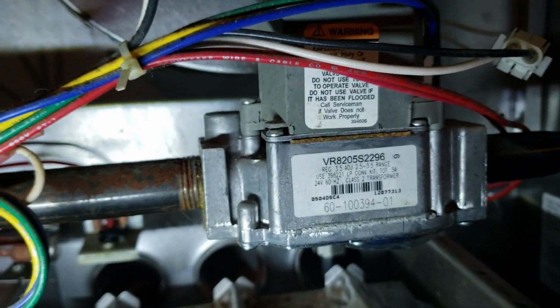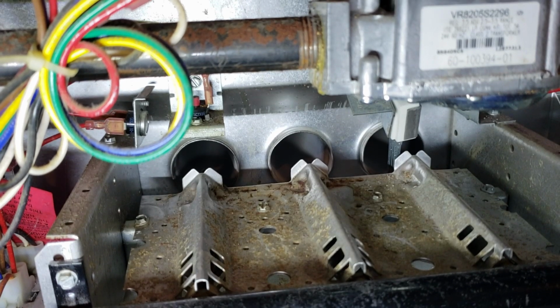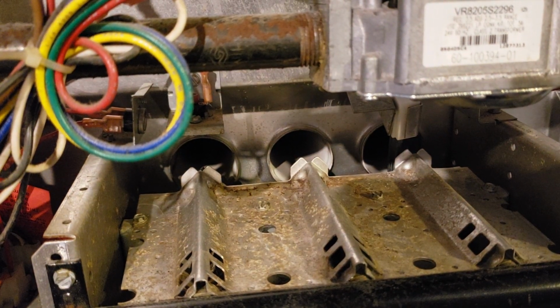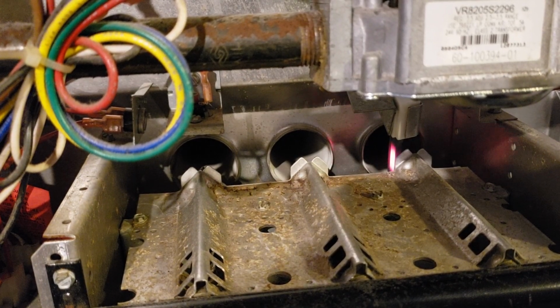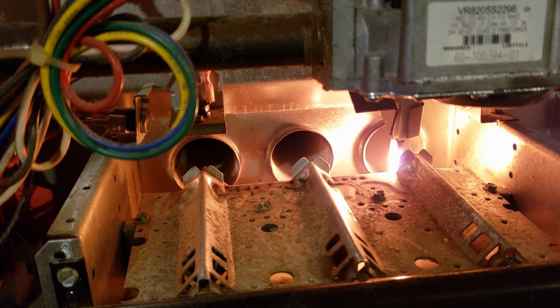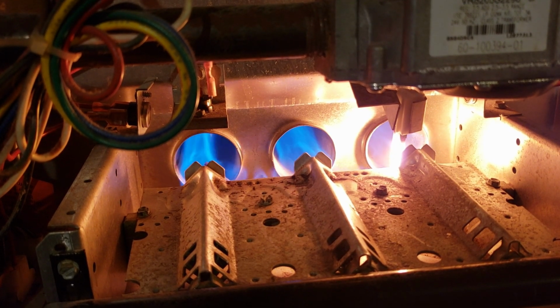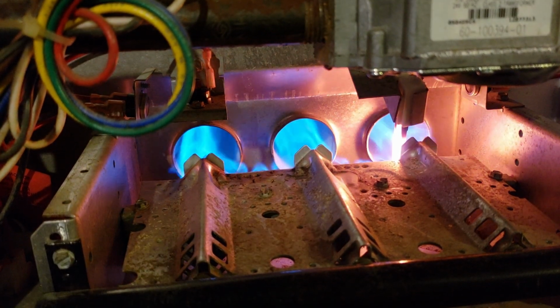All right, let me move you in here, and then let me put this door panel on, and we'll see if it glows and lights up. Okay. Spinning. I wonder if I should turn the light off so you can really see it glow. Hopefully. Once the gas hits, hopefully it'll... There it goes. She's lighting. That's what we needed. And we'll watch it kick off, hopefully. There it goes. Hey, we're working yet again.